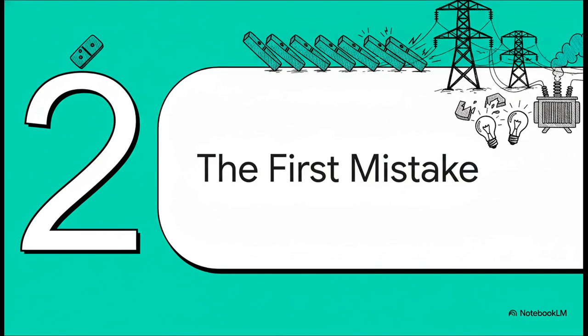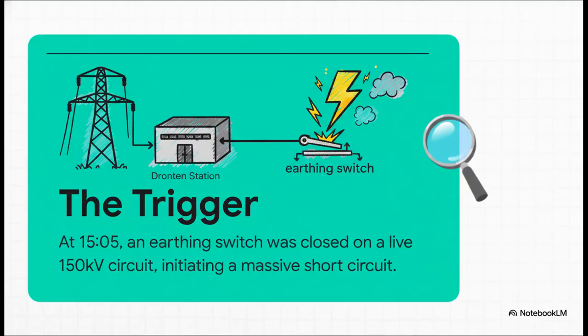Well, like a lot of disasters, it started with a single, seemingly small action. At 3:05 in the afternoon, a technician at that new Dronten station closes an earthing switch. Now, these switches are a super important safety feature. They're designed to connect a power line to the ground, making sure it's de-energized and safe to work on. The problem was, in this case, the circuit was very much alive. Closing that switch created a direct path for 150,000 volts straight to the ground, and boom, you've got a massive short circuit.